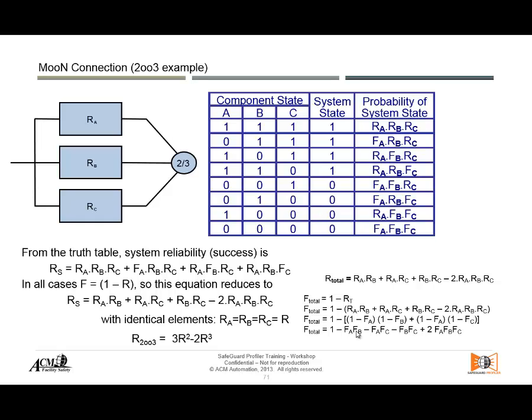The two-out-of-three is a special case — it sits in the middle of the tug-of-war between success and failure, giving the best of both worlds. From the Safeguard Profiler point of view, if all elements are the same we can group them into a simplified formula. However, we have not yet included the common cause factor — the beta factor — which must be added for both the 1oo2 and 2oo3 configurations.